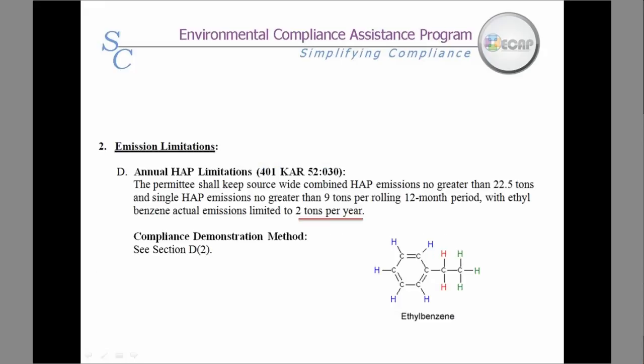Another type of a true emission limit is when a limit is imposed for a particular pollutant. This occurs often when an air toxics assessment indicates that a particular level of a defined pollutant is determined to be hazardous to human health or the environment when above a certain level. For example, this conditional major permit requires rolling totals of HAP and VOC emissions, except the air toxics assessment indicates the facility cannot emit more than two tons per year of ethyl benzene.